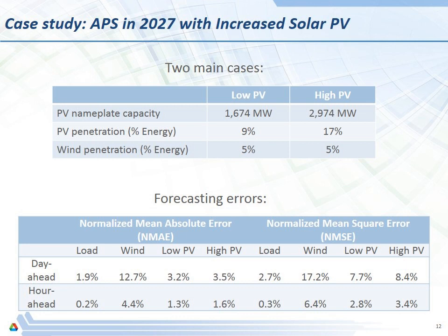And so in order to model these scenarios, we developed 1-minute data sets of wind, PV, and load. And the 1-minute data sets are based off of hourly satellite-derived data, which we then add 1-minute variability to based on methods that are described in the appendices of the report. The key to understanding that methodology is that we try to account for correlation between the different sites and also the expected variability that you would have within each individual site based on the cloudiness level experienced during that hour. We also have day-ahead forecast errors for the load that were provided from APS, and then we have day-ahead forecast errors from wind and PV.